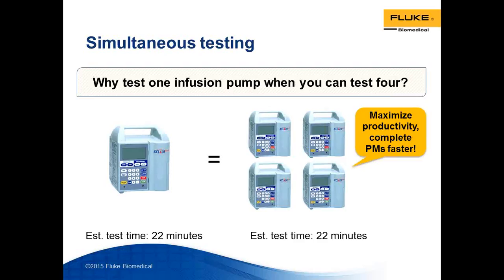So what this slide is showing you is that with an analyzer, when you do the testing, it takes about 22 minutes to perform the test from start to finish, including setup, testing, and documentation. So you're shaving off 8 minutes right there. But imagine doing that with 4 pumps simultaneously - you're quadrupling your savings because you're testing 4 pumps in 22 minutes.